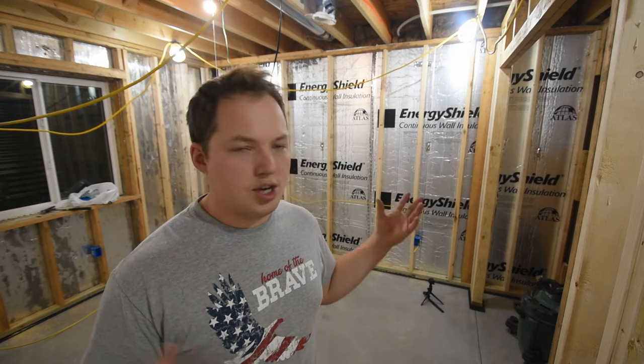You could theoretically pull power from another circuit as long as that circuit had additional capacity available. Now let me explain a little bit more how you can calculate that. The general rule of thumb for when you're calculating how much power you need for a given space, for general purpose lighting and receptacles, not for dedicated appliances like a washing machine or dryer, is calculated out based on square footage.